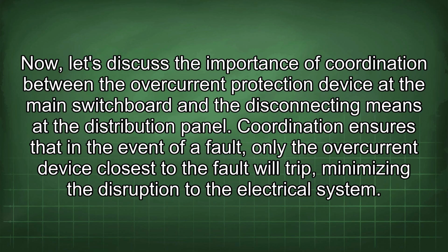Now let's discuss the importance of coordination between the overcurrent protection device at the main switchboard and the disconnecting means at the distribution panel. Coordination ensures that in the event of a fault, only the overcurrent device closest to the fault will trip, minimizing the disruption to the electrical system.